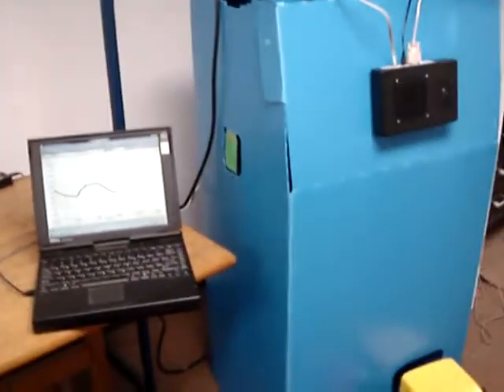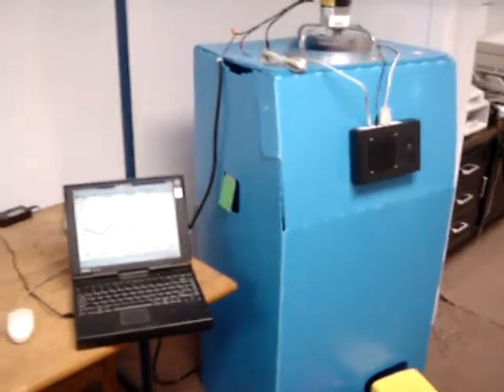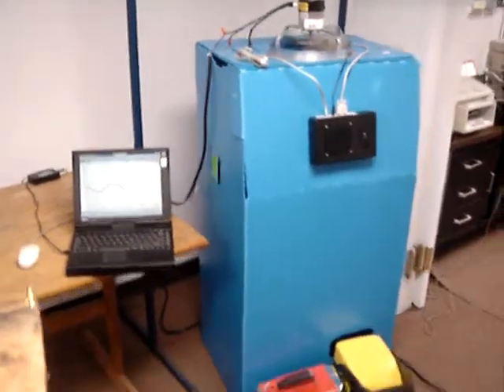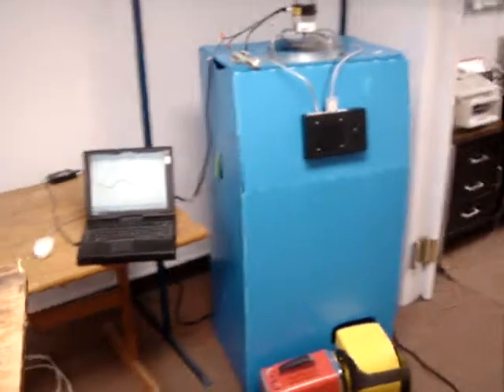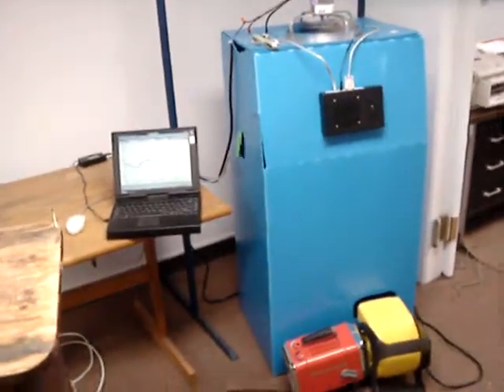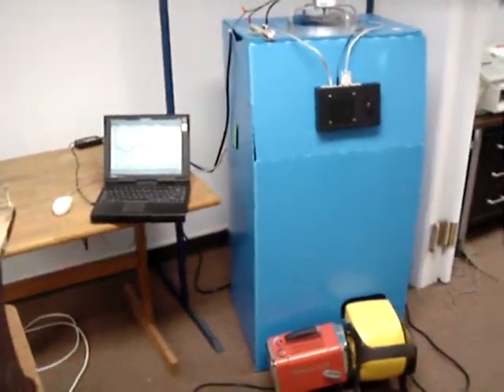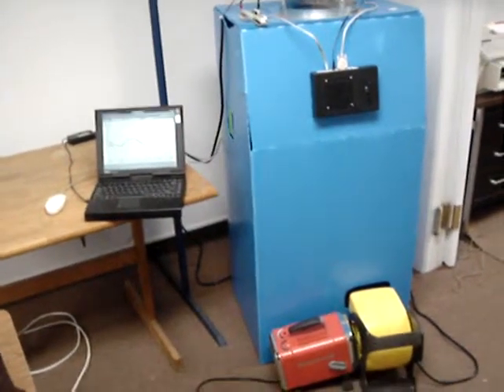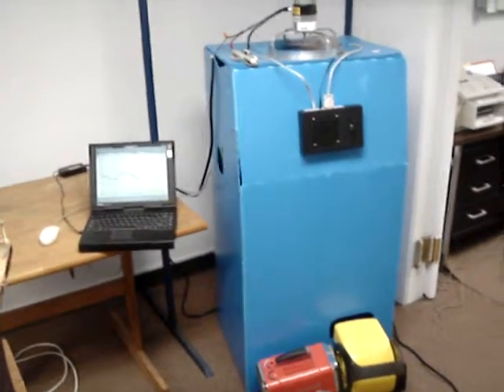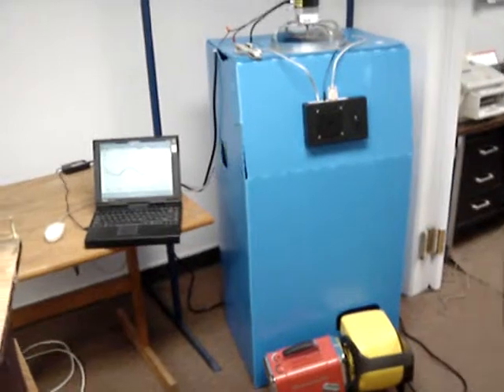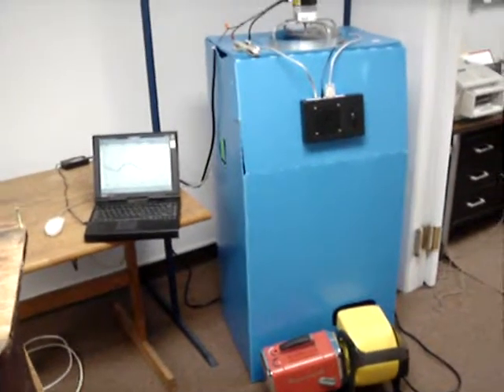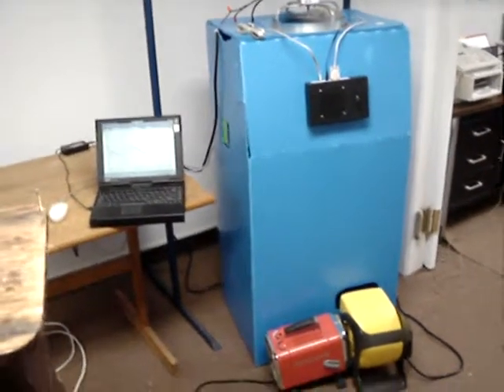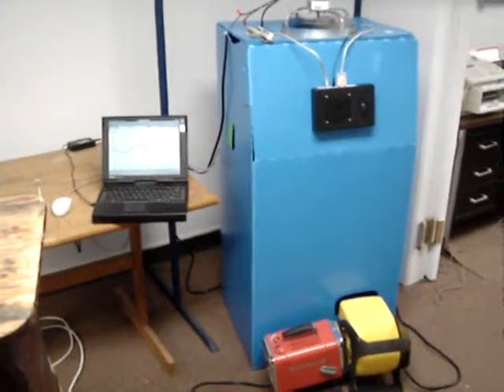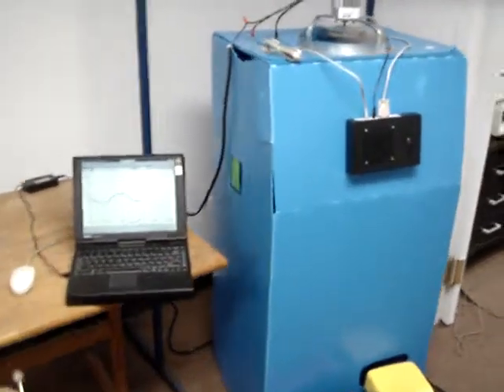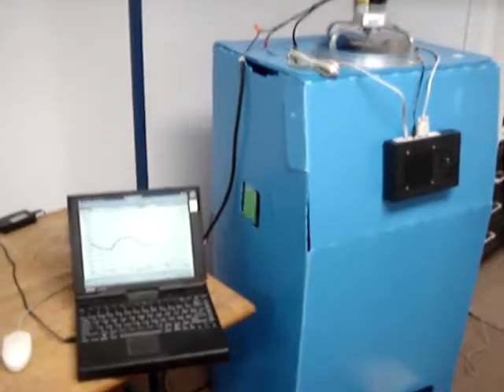So that's pretty much it. That's a quick demonstration of the CFM matching technique. And we've actually tested this on real server racks as well, with fans on top of the server racks and fake heat loads, not real servers, but it performs in the same manner. So that's a demonstration of the CFM matching technology.